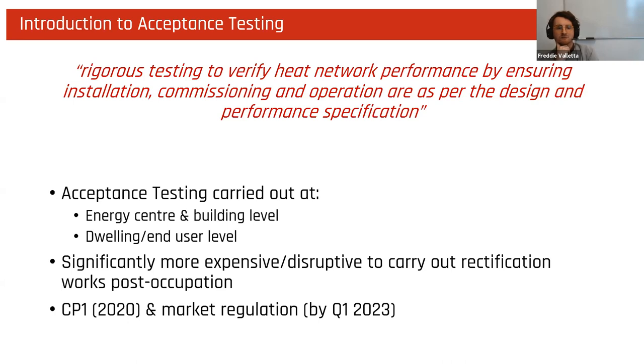Typically, this term has been focused on dwelling level tests. However, now it's being introduced as a coverall term applying to performance tests carried out in the energy center and at a building level as well. This process was developed to ensure that all performance issues with individual units and the system as a cohesive unit are addressed, as it's significantly more expensive and disruptive to carry out rectification works post-occupation.